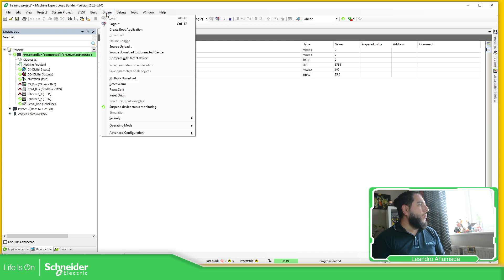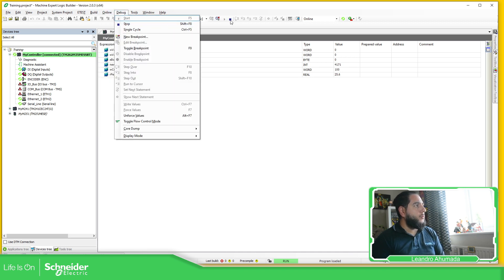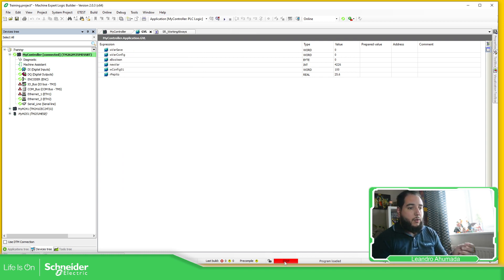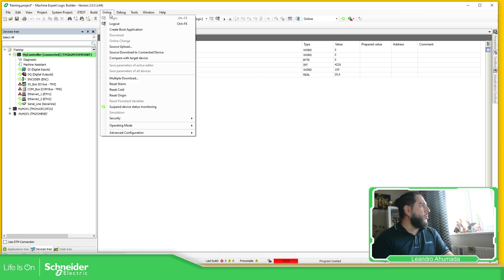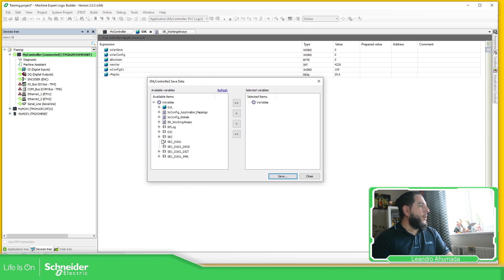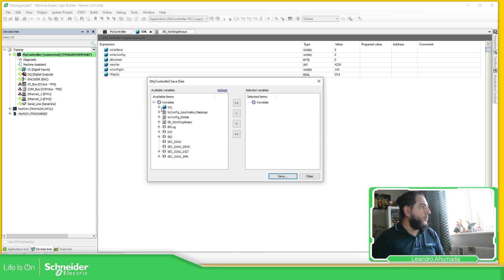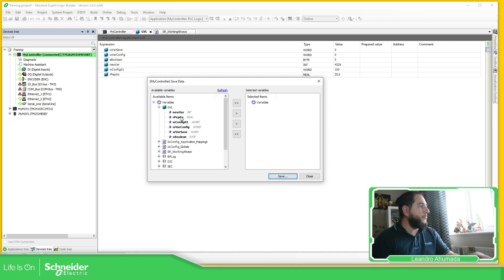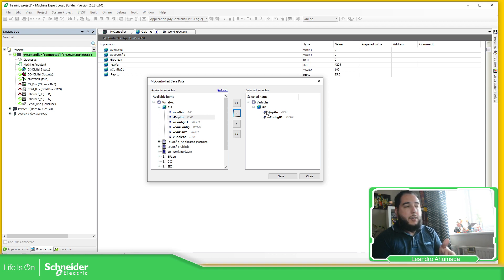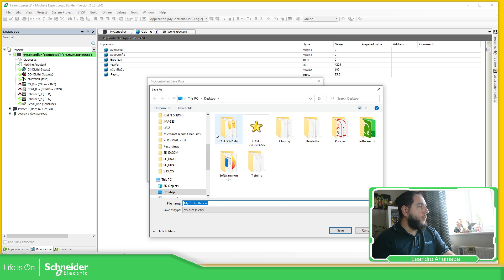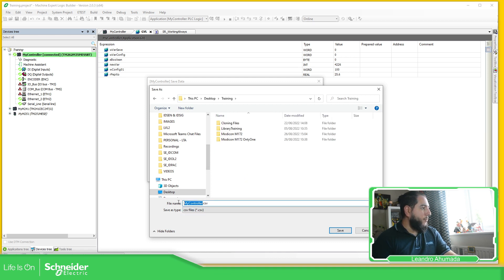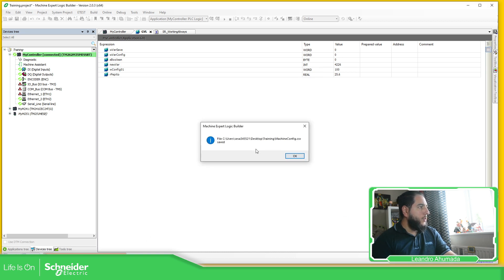What we need to do is go to Online, Debug, and stop the controller — you can see the red message at the bottom indicating it has stopped. Go to Online, Advanced Configuration, Save Data — this view. You can see here what I have in the project: the GBLs, the SR working, everything. I'm going to move Pepito and config_01 to the other side. You can see the name of the GVL and the two variables. Now I'm going to save this file as 'machine_config'. The file has been saved.